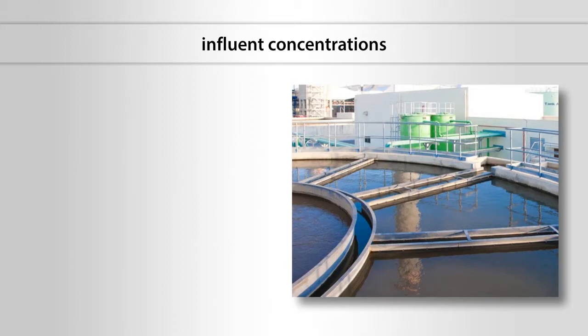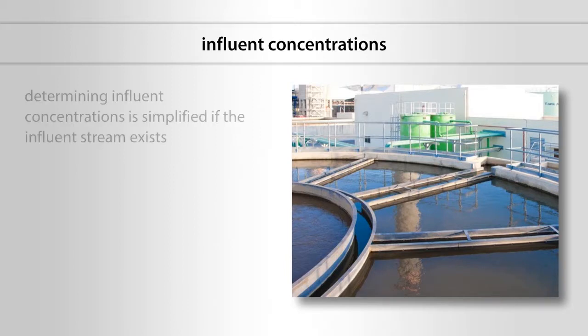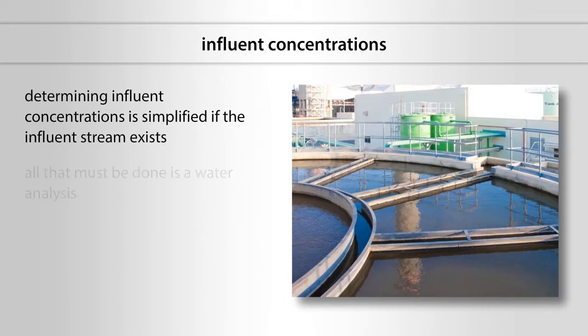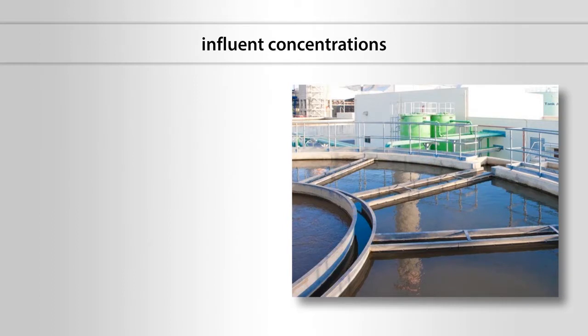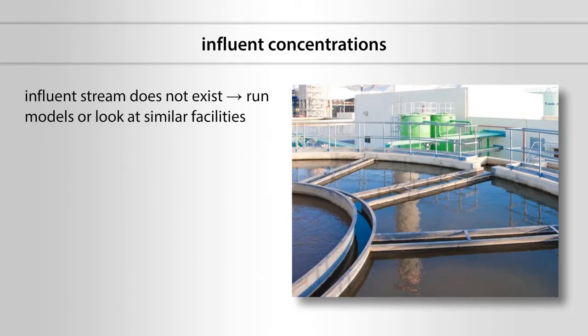Influent concentrations for the contaminants of concern are the second important design criterion. Determining influent concentrations is greatly simplified if the influent stream currently exists — all that must be done is a complete water analysis. However, the influent stream frequently does not yet exist, as in the case of an entirely new industrial facility. In that case, scientists and engineers typically run models or look at similar facilities to estimate average concentrations or a range of possible concentrations.